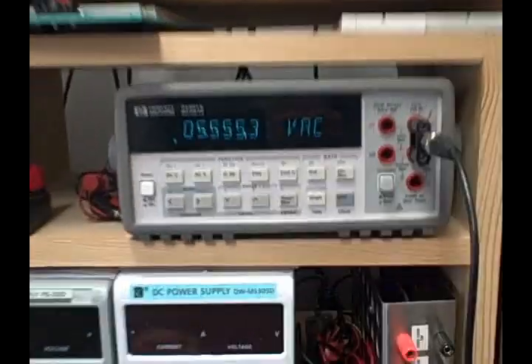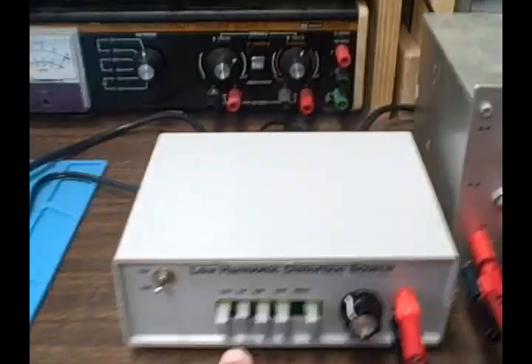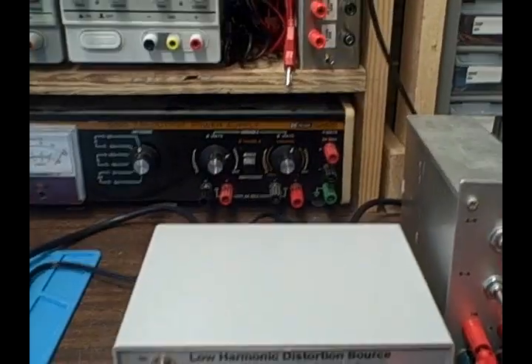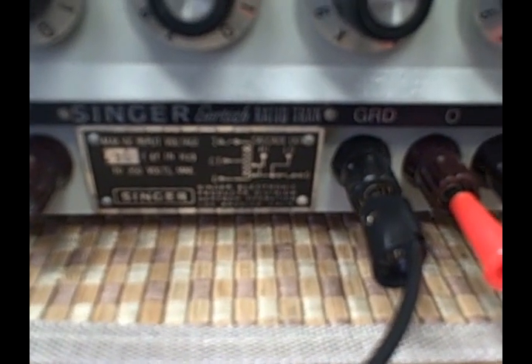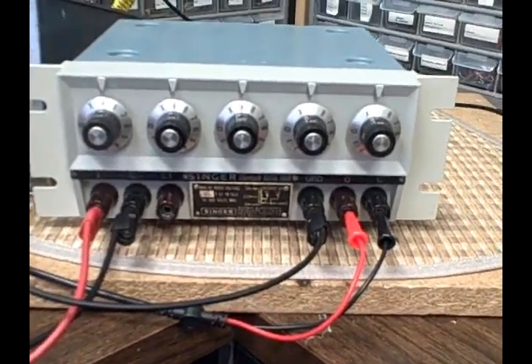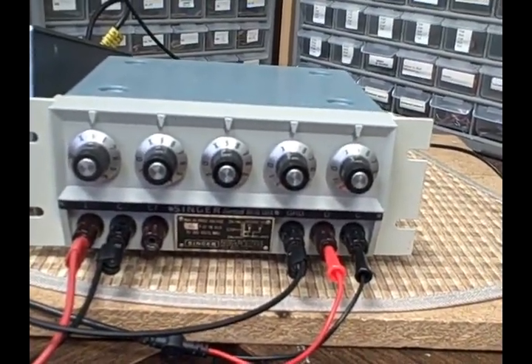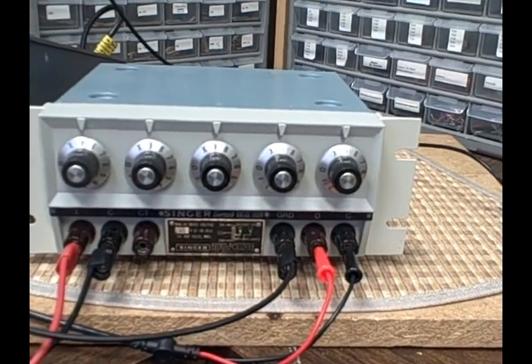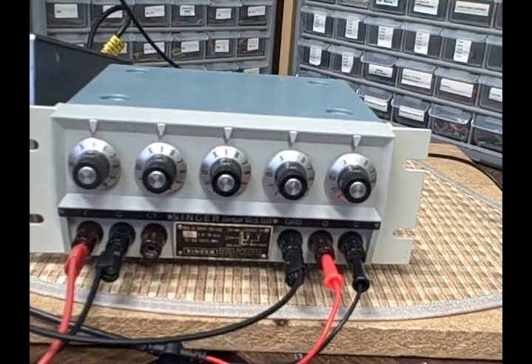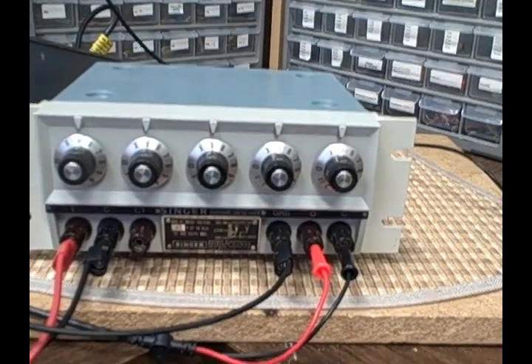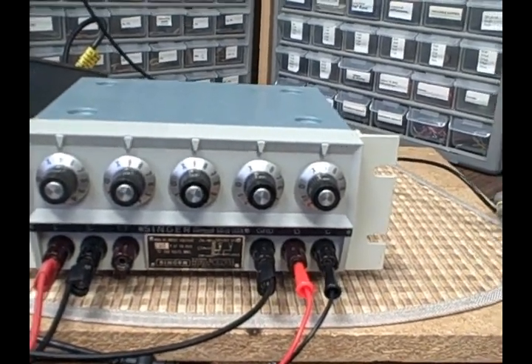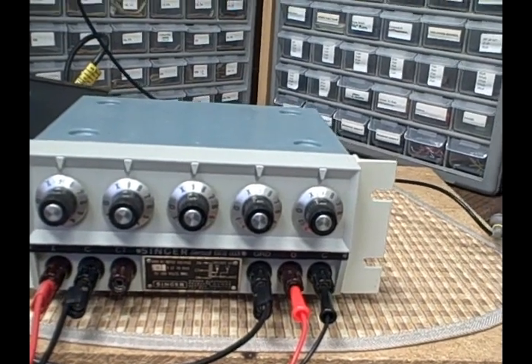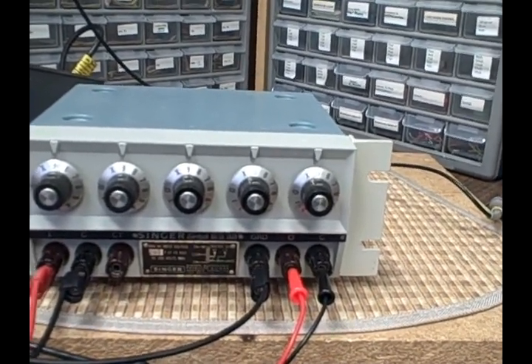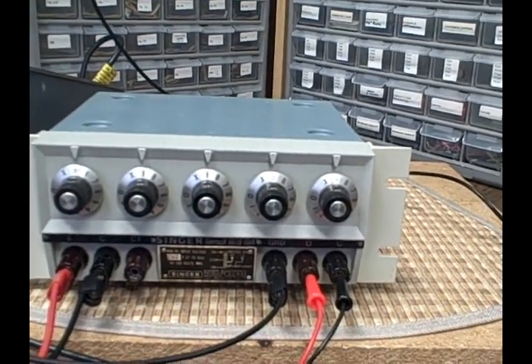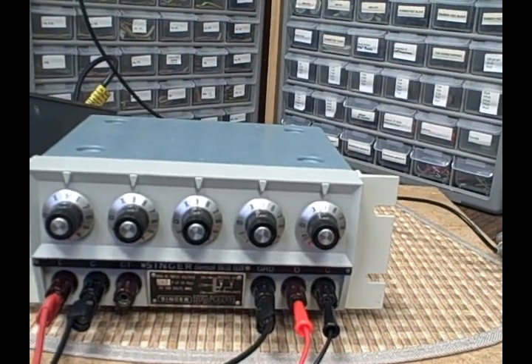Now I could use that voltage, that calibrated AC voltage. I've chosen 1 kilohertz. I had 100 kilohertz. I could throw 10 on here, but I have to be careful that I don't overdo the plate value of input voltage. According to the front plate, my maximum frequency has to be such that 0.35 times my frequency must be less than or equal to 350 as a number, and that turns out to be the volts they're discussing. Another way of looking at that would be to say 350 volts over 0.35, and that would give me 1,000.